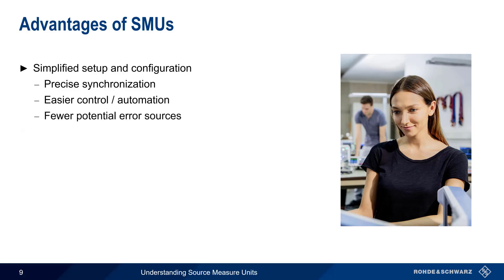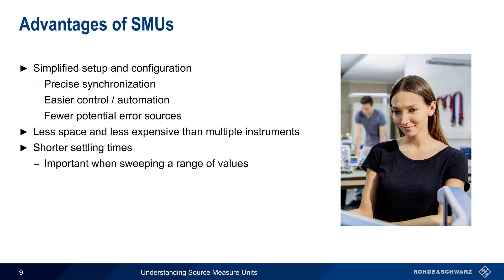In addition to the ability to operate in different quadrants, source measure units have a number of additional advantages. They are easier to set up and configure due to the fact that both source and measurement functionality are integrated into a single instrument. This in turn provides very precise synchronization, easier control and automation, and fewer potential sources of error. One instrument also takes up less bench space and is usually less expensive than using multiple instruments. But source measure units offer advantages that go beyond the simple integration of source and meter. Source measure units usually have shorter settling times, that is, how long it takes the source output to reach a stable state. This is important when we need to sweep a range of values and make a large number of measurements, since shorter settling times translates into a faster overall measurement. Furthermore, source measure units generally have much higher precision and a wider operating range than stand-alone power supplies or digital multimeters.